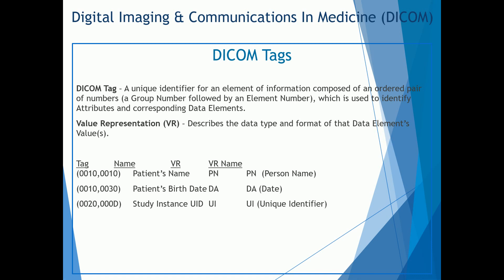Any device that sends images to a PACS system — you'll know that if you open up that study and view the contents of the DICOM headers, and we'll go into details on how to do this in the actual workshop, you'll see this in action. When you see (0010, 0010), you'll know that relates to the patient's name and it'll show the actual patient's name. Similarly, (0010, 0030) is the patient's birth date.